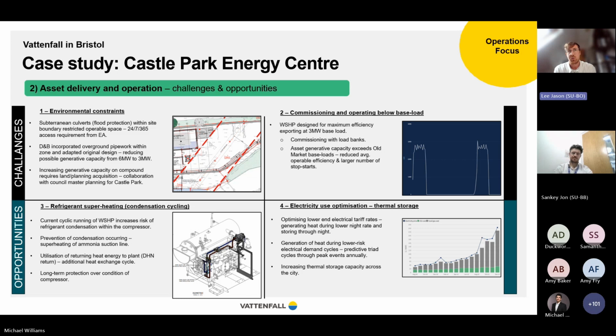Some of the opportunities that I've identified. First of all, we worked with the OEM on a refrigerant superheating system, to directly address some of those stop-start cycles that we see on our asset. Essentially, with the cyclic running of the heat pump as we see today, we do have the risk of refrigerant condensing within the compressor. That can cause long-term damage over time. So we have utilized some of the returning heat to the site from our DHN to superheat that ammonia suction line to the compressor, which will see a very long-term benefit of protection of the compressor before and after we reach that base load.